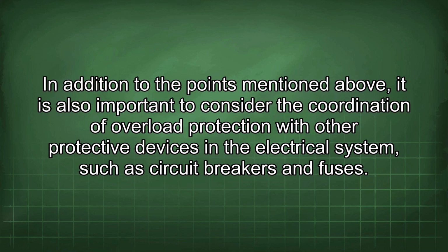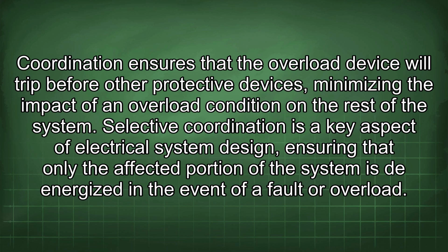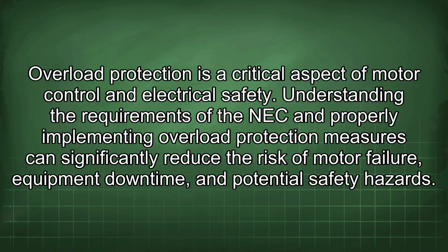In addition to the points mentioned above, it is also important to consider the coordination of overload protection with other protective devices in the electrical system, such as circuit breakers and fuses. Coordination ensures that the overload device will trip before other protective devices, minimizing the impact of an overload condition on the rest of the system. Selective coordination is a key aspect of electrical system design, ensuring that only the affected portion of the system is de-energized in the event of a fault or overload. Overload protection is a critical aspect of motor control and electrical safety.